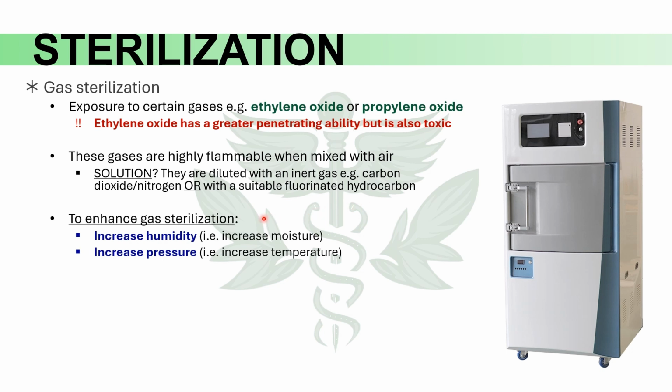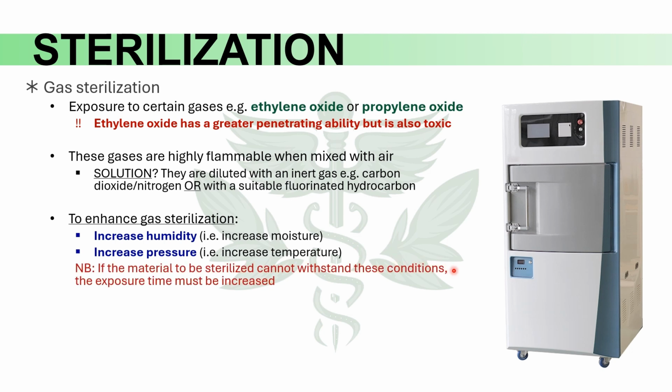There are certain things that we can do to enhance gas sterilization. We can increase the humidity and the pressure of the system, but this only holds true if the material to be sterilized can withstand these conditions. If it cannot, then the exposure time is simply increased to achieve the same results.